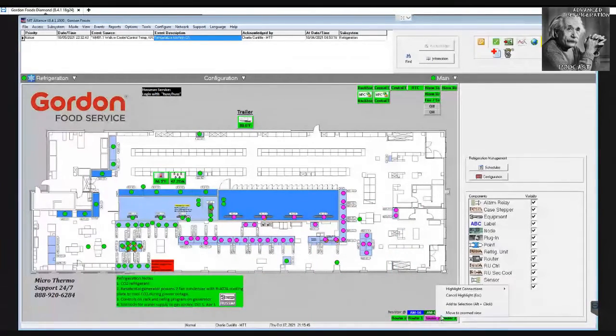So you just do the highlight or cancel highlight. Now, when you are looking at the visualized network connections node to node, as long as every dot you see here is green, that means every set point is perfect—every temperature, every pressure is correct. If one of these nodes should ever go black, that means you've lost connection. Visually, if you see a black node, it's lost its echelon communication. If one of these nodes were white, it means it's not been configured completely. So it's stoplight: green is good, yellow's caution, red is bad.